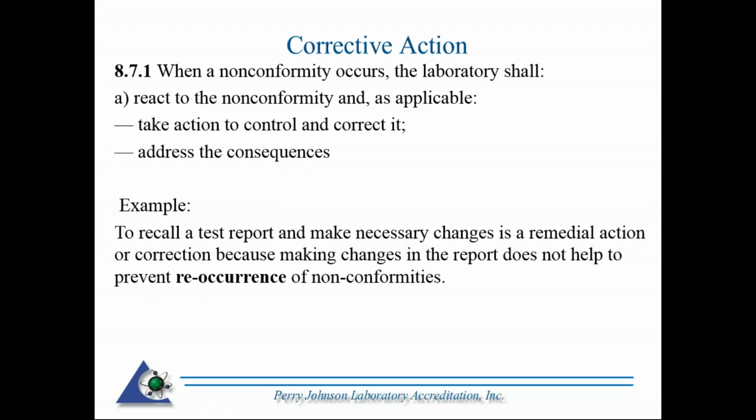An example I give there is if you have a test report, a client calls in, there are errors on the report, the correction or remedial action would be making the required changes in the report and reissuing it. That, however, if this is, let's say, an ongoing issue, it's happened several times within a short time span, or you are continuously putting Band-Aids on the situation, just reissuing the report will not prevent recurrence of the nonconformities.